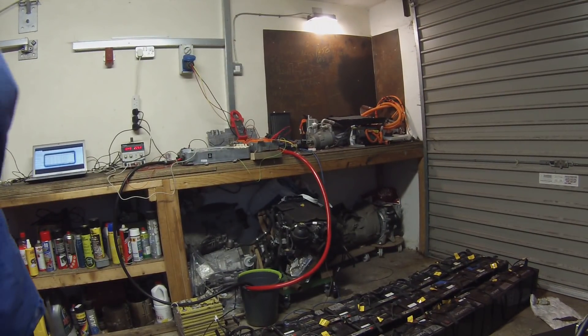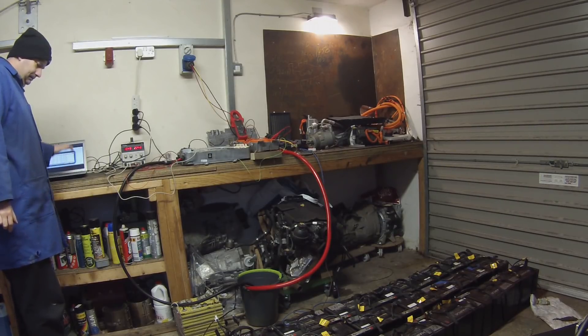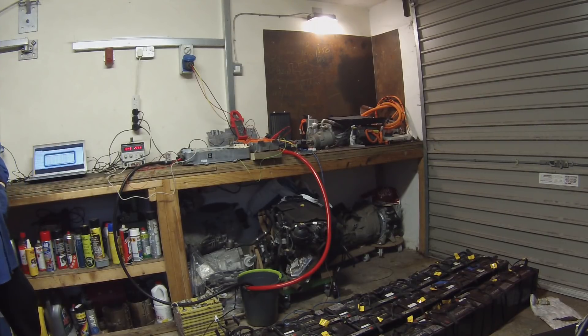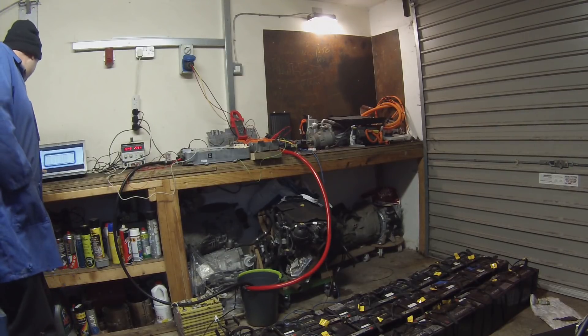About 1.2 kilowatts — you don't want to see low power stuff, we need to see high power stuff. We're going to wind it up gently just so we don't go bang. Let's go C4. We're now commanding 4 amps per module, so we're now about 11 amps on the battery and 2.5 kilowatts in. Let's go for 5 amps.